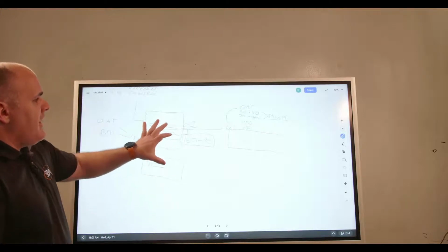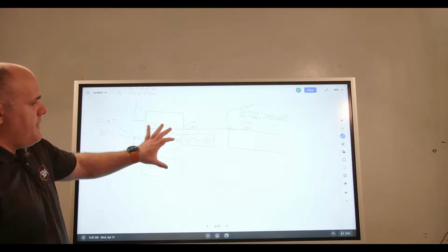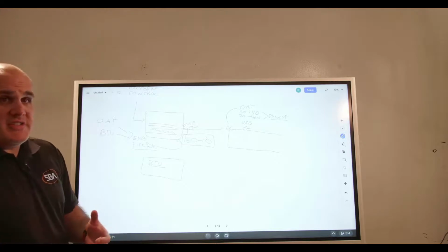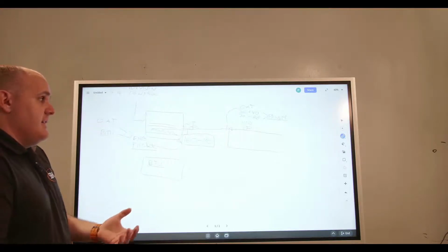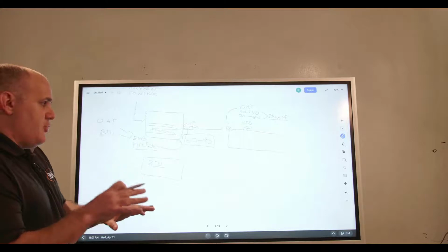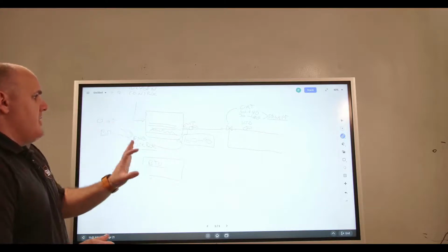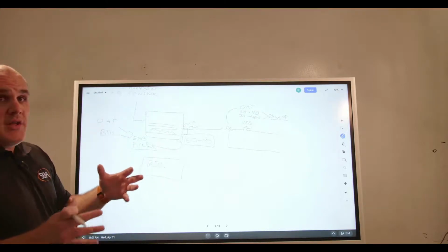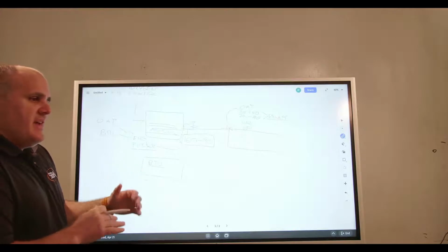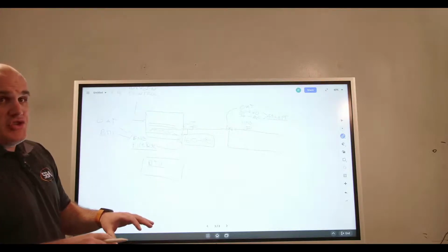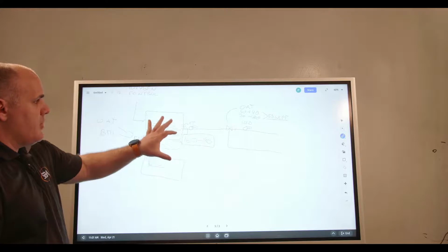Because if I want to stage these boilers up, there's unison, there's lead lag, and then there's kind of staged where you just step them up. I like unison control, where you run both boilers in unison and you vary their fire rate and you track, and in most cases that can work really nice.